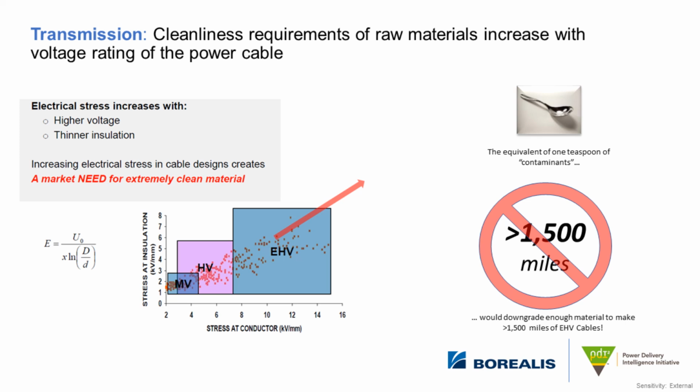No, not really. And the standards don't really allow for that either. The medium voltage distribution cables that are made today will operate perfectly well in a wet, submersed environment their entire life. There's a lot of cable in cities that you open the manhole and it's wet. It's always wet. There's water in there. You have to pump them before you go in. And that holds true for distribution cable vaults as well as transmission cable vaults. I've been in a number of them when I was working in the construction side of this business. There are a lot of vaults in this country that are full of water all the time.